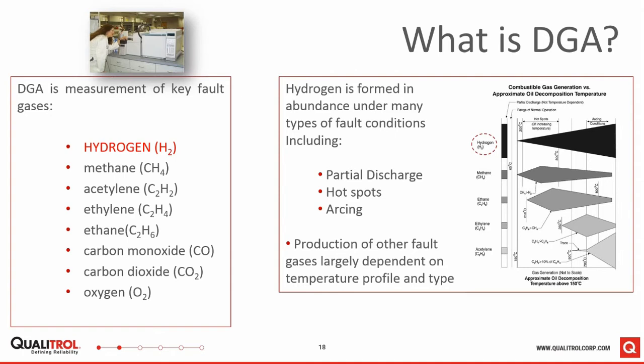So DGA is the measurement of 8 gases found dissolved in transformers. They're called the 8 key fault gases, and they have been established by various industry bodies and researchers, with this technique emerging in the 1970s and evolving ever since then. Ideally, in a vault application, we would monitor all 8 gases. However, 8 gas DGA tends to be prohibitively expensive, and it tends to require reasonably easy access to the transformer and the monitor itself.